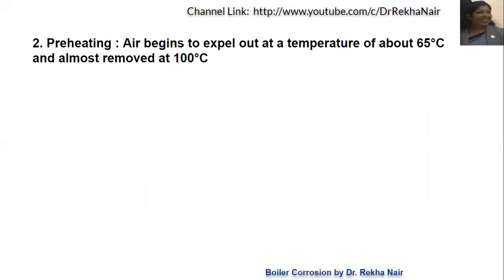Next, we can preheat the water. Air begins to expel out at a temperature of about 65 degrees centigrade and is almost completely removed at 100 degrees centigrade. So if you preheat the water, that oxygen can be removed.